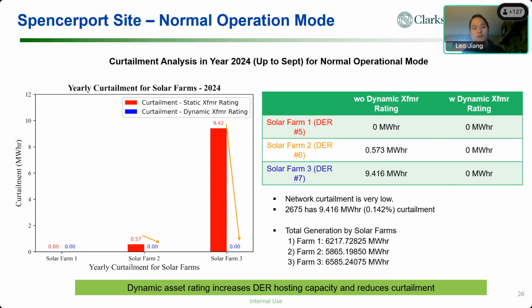We did this study for the Spencerport site. As Zach already illustrated, in the demonstration Avangrid doesn't really see a lot of curtailment, though in some cases we do have thermal constraint curtailment. You can see that if you implement dynamic asset rating here, in this case using the transformer rating, by the way, the red and the blue are before, with the static and with dynamic rating. For this case, with additional capacity, ideally the network congestion related curtailment can disappear. But regardless, the curtailment for 2024, which is what we analyzed, is low.